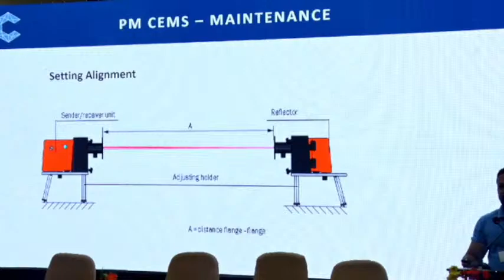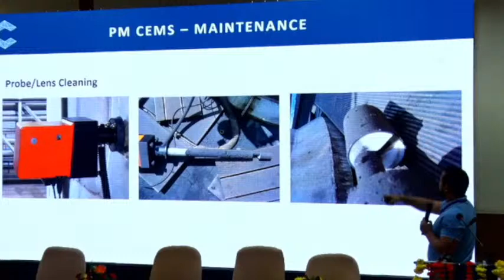You have seen the cover, dust particles settle on that probe. You keep cleaning it. Over the probe, it is not affecting, because monitoring is not on this. Monitoring is in between this portion, right? So the light source goes from here and the reading is happening here. So in the ideal condition, we should keep it clean for sure. It is not that monitoring is not happening here, so leave that. This portion should also be kept clean.